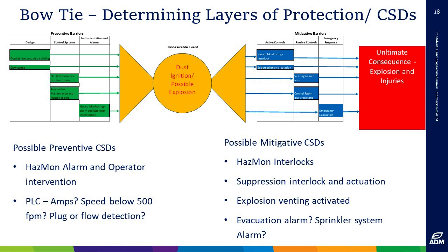Gas detection systems, our carbon dioxide sensors that I mentioned. Smoke and fire detection. Process alarms, if we're requiring that alarm to have a person do an intervention to stop something. So not all alarms. And maybe we suffer from this, and maybe others do, of way too many alarms. You have an operator sit down, and there are 50 alarms up. Which one matters?